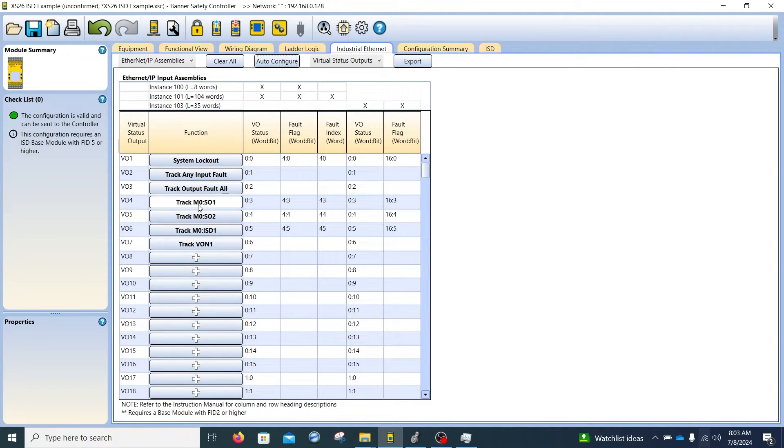If we're interested in safety output one — which is Track M0:SO1 — that tells us in the Rockwell input assembly instances that it's going to be word zero bit three, which will go on and off to track the status of safety output one. There's a lot of information available here. For example, if you want to know if a connection is faulted, that's word four bit three. You can look in the Banner Safety Controller manual for definitions of all these titles.